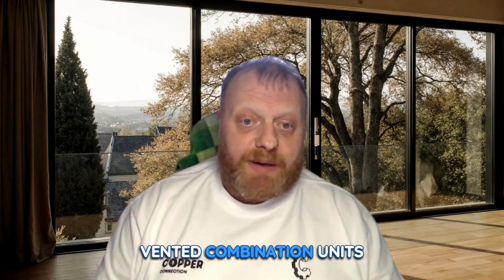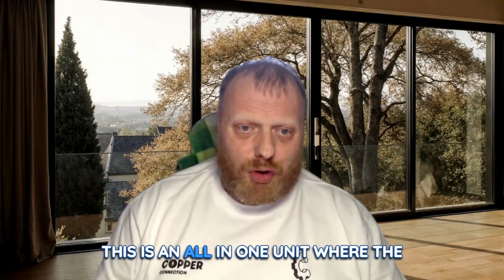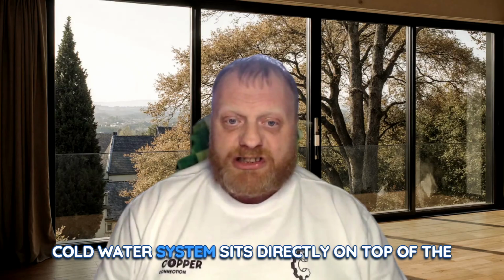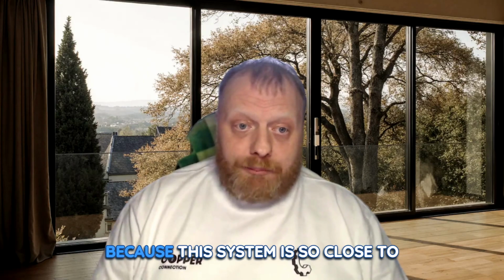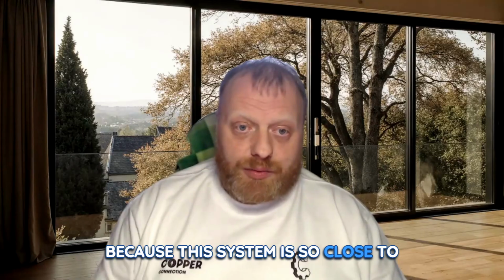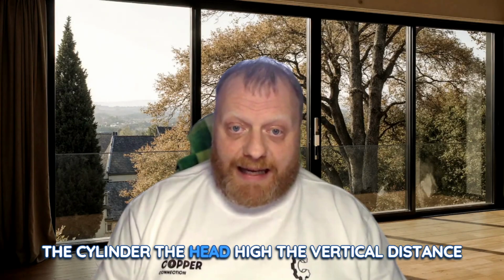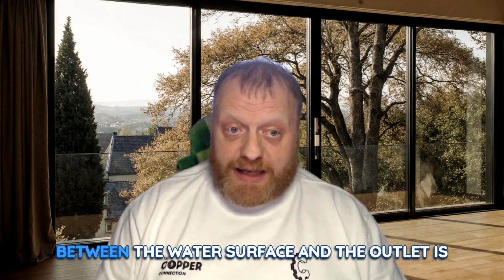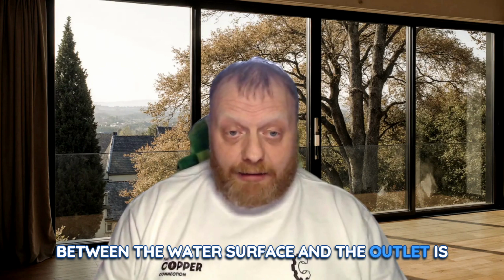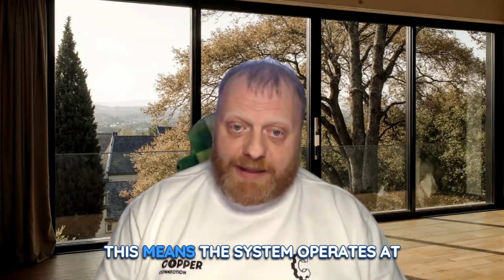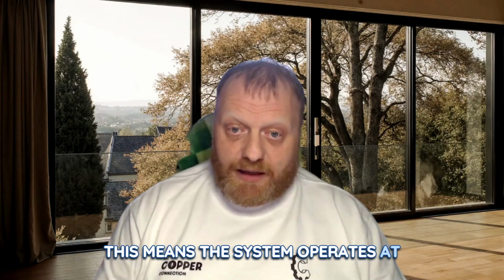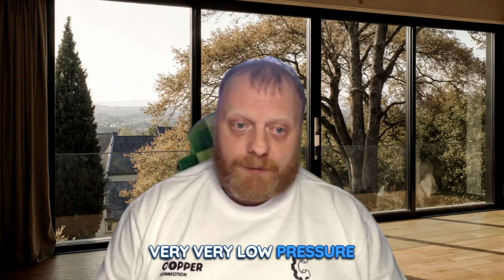Open vented combination units, or Gledhill-type cylinders. This is your all-in-one unit where the cold water system sits directly on top of the hot water cylinder. Because this system is so close to the cylinder, the head height, the vertical distance between the water surface and the outlet, is very small. This means the system operates at very, very low pressure.